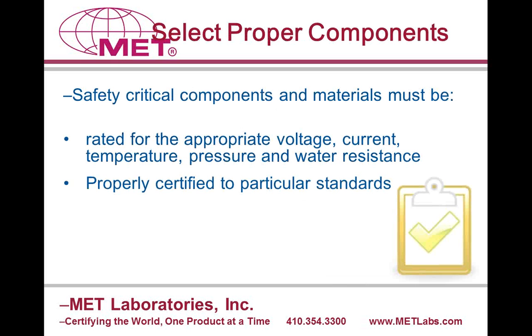Usually you know what voltage you can expect the system to run on, and there will be components that have to be rated for that voltage. In terms of current, some equipment like your pumps and heaters and motors will act as a load, and other equipment such as your fuses, circuit breakers, and terminal blocks need to be able to bear that load. Your pumps and piping must be able to withstand the pressure they'll see. Your cords and enclosures need to be water resistant. And on top of that, your components need to have safety certification to ensure that they'll meet safety requirements on their own.